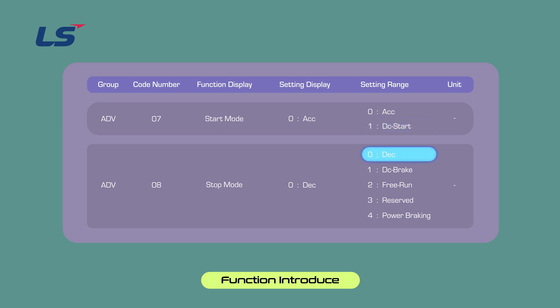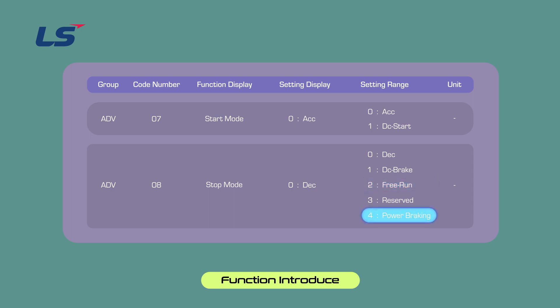DEC Stop method is a general deceleration stop method. If there is no separate function selection, it decelerates to 0 Hz and stops, reflecting the deceleration time. The DC Brake stop method can be used when you want to stop the motor by applying DC voltage at the set frequency during deceleration. Free Run stop method blocks the AC drive output when the operation command is turned off. Power Braking stop method controls the deceleration slope or re-accelerates to reduce regenerative energy when the AC drive DC voltage rises above a certain level due to motor regenerative energy.